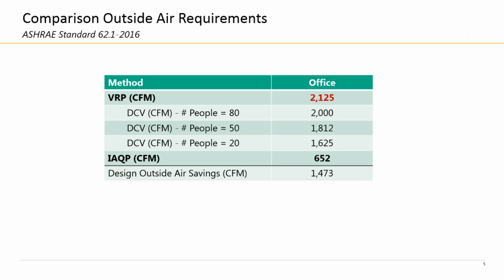Here's an example of how ventilation rate procedure, demand control ventilation, and the indoor air quality procedure might break out on a standard, let's say, 20,000 square foot building. If you're ventilating according to VRP in the ASHRAE standard calculations and tables, you might be required to bring in 2125 CFM of outside air. If you apply CO2 sensors to each of the spaces, then you can drive down that outside air. You can modulate those outside air dampers down based on the people component within that space. But that eventually hits a floor, and that floor is about a 30% reduction in office buildings versus ventilation rate procedure. With the indoor air quality procedure, as long as you're able to scrub for all the contaminants being emitted within that space, CO2, formaldehyde, ozone, etc., you can actually drive that outside air down, in this case, to 652 versus that original 2125. So that is a significant outside air reduction versus demand control ventilation.